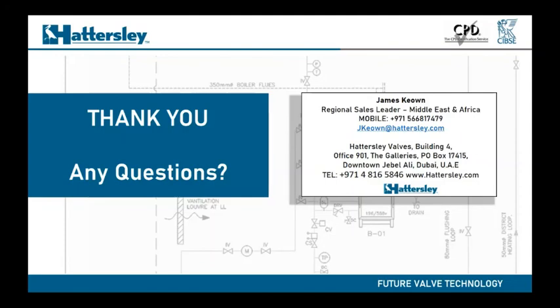So Syed Hussein is asking us, what is the accuracy of H&H PICV on the bronze range and large diameter ferrous ones? Accuracy, it's around about plus or minus 10%, I believe, on some of the valves. With the larger valves, I think they're more or less plus or minus 10 to plus or minus 15. It does depend on the size. Some of them alter within the bronze range as well, but generally they're between plus or minus 10 and plus or minus 15 worst case scenarios.